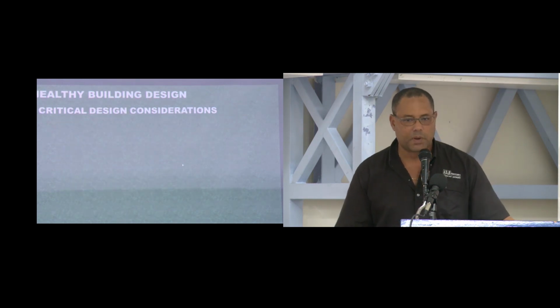So what are some of the critical design considerations for a healthy building? First of all, you've got to know what the usage is going to be, what sort of activity. If you're designing for the aforementioned call center, obviously your occupant density is very high. If you are designing for an office, then you know what the average density of an office is going to be. Or you do have a floor plan that indicates these many people are going to be in here, and this is the sort of activity. A caution to people who design speculative office buildings, from the landlord's perspective: if an office building is approached by a call center, they either have to do some serious retrofitting or you have to turn them down.